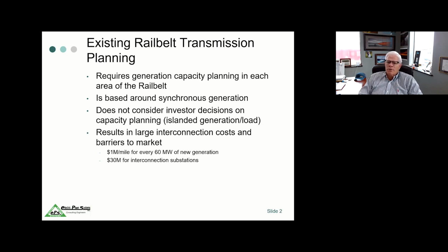The other thing the existing system does, because it's a transmission deficient system, is there's not a lot of interconnection possibilities for renewable operations. There are only a few transmission lines that can support renewable operations or connections currently. In addition, for every 60 megawatts of generation, which is the largest generation resource allowed on the Railbelt at this time, your 230 kV transmission line costs about $1 million a mile, and you have about $30 million for interconnection substations on each end.